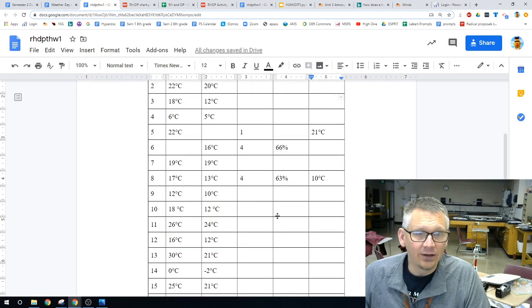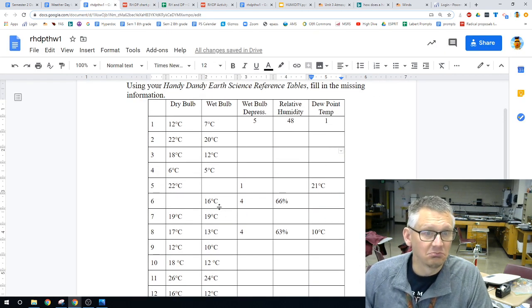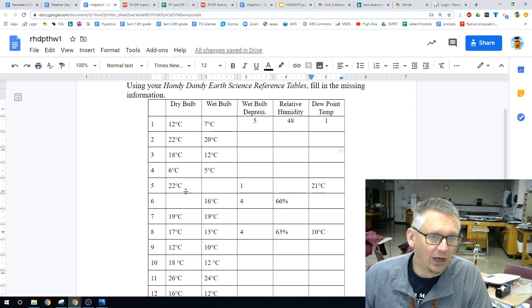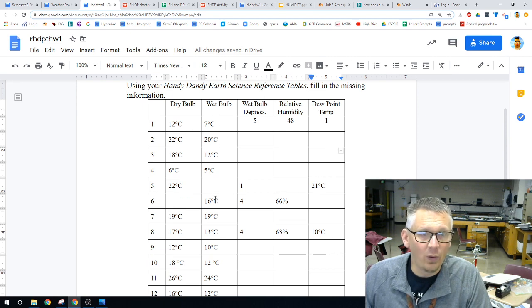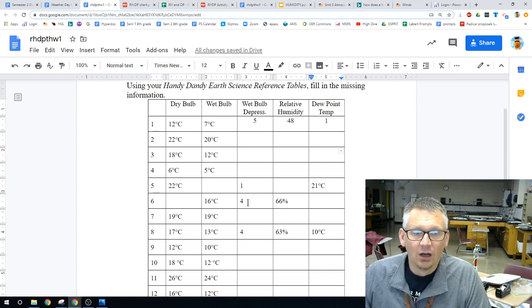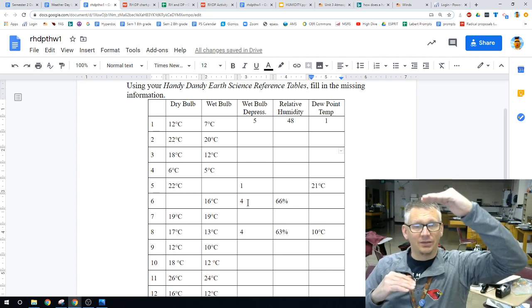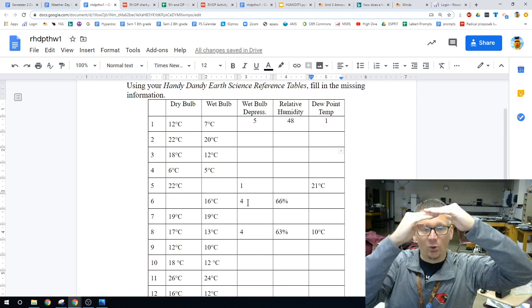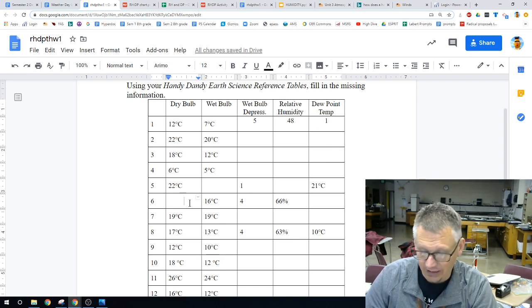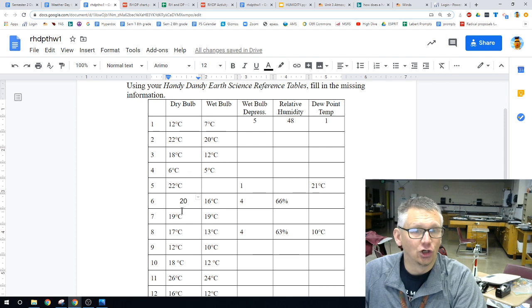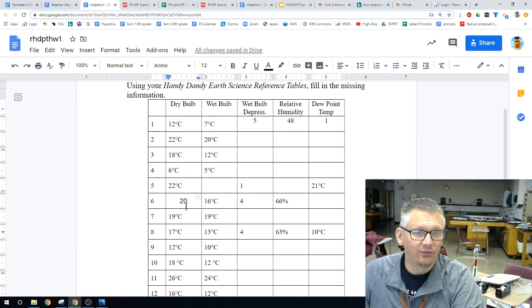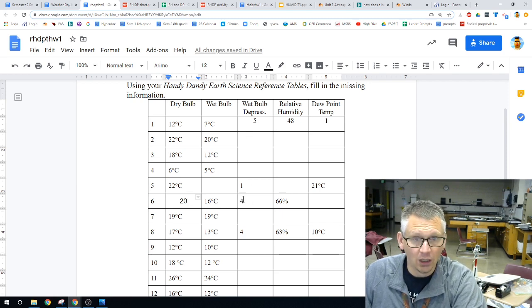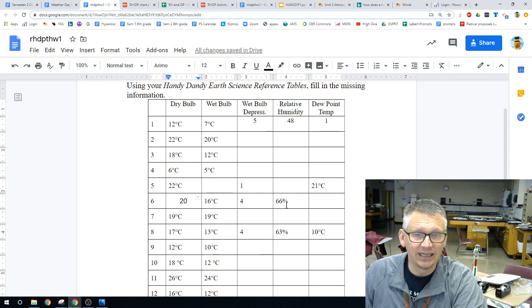If we come down here and let's take a look at number 6. Number 6 is a little bit different. It says our wet bulb is 16, but it has a depression of 4. Well, that means our dry bulb is up here and our wet bulb is down here. The difference between them is 4. So, our dry bulb must be 20. We have a dry bulb of 20, a wet bulb of 16. We have a depression of 4, which gives us a relative humidity of 66.